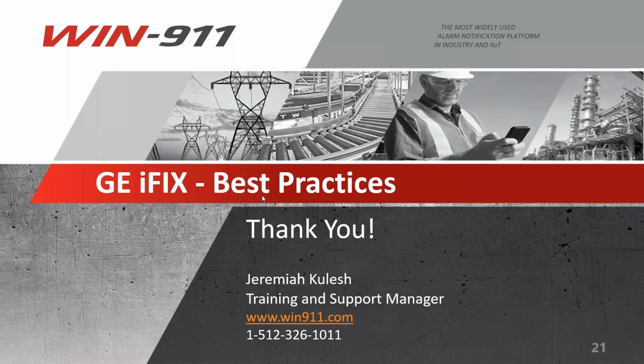Next question here: can the WIN-911 user account be a domain account if iFIX utilizes Windows accounts? We always recommend just using a local admin account. WIN-911 can absolutely run as a domain account, but again, it's highly recommended to just use a local admin. That domain admin should be a member of the local admins group anyway, if you're doing things right on the domain side.